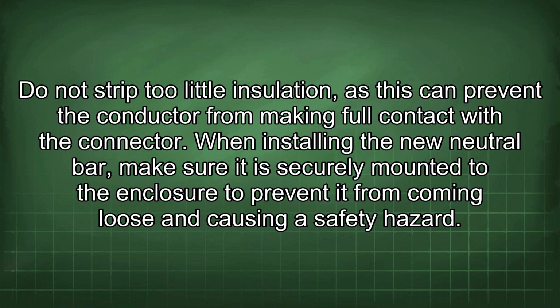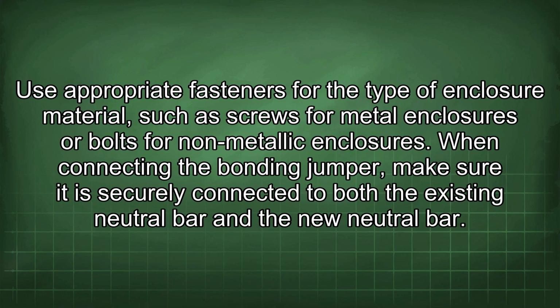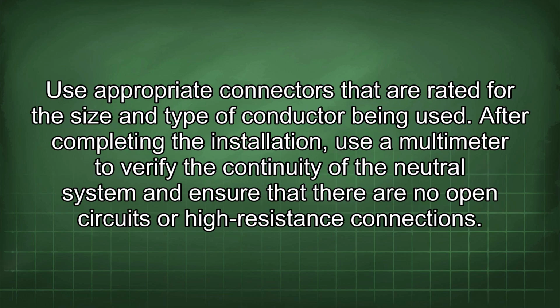When installing the new neutral bar, make sure it is securely mounted to the enclosure to prevent it from coming loose and causing a safety hazard. Use appropriate fasteners for the type of enclosure material, such as screws for metal enclosures or bolts for non-metallic enclosures. When connecting the bonding jumper, make sure it is securely connected to both the existing neutral bar and the new neutral bar. Use appropriate connectors that are rated for the size and type of conductor being used.